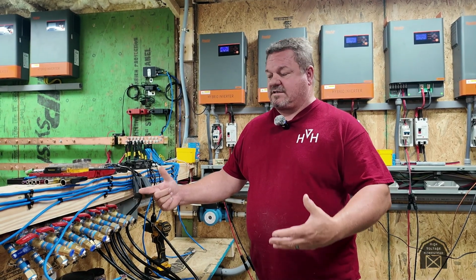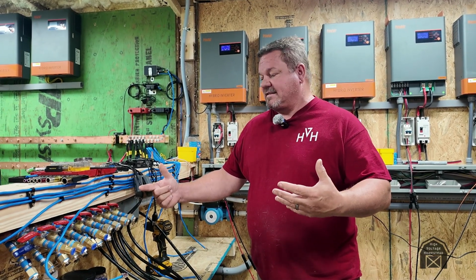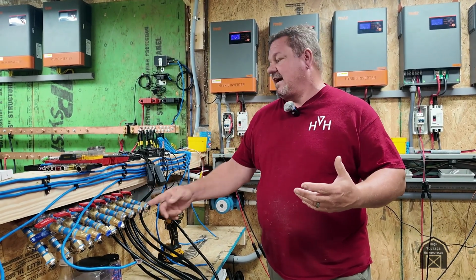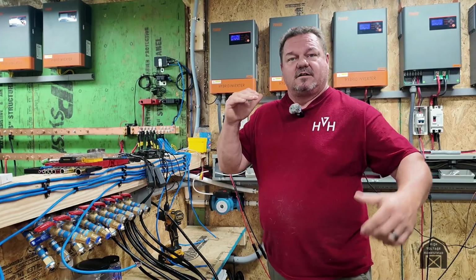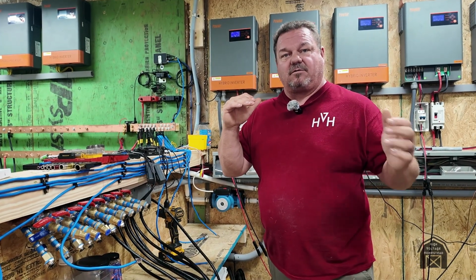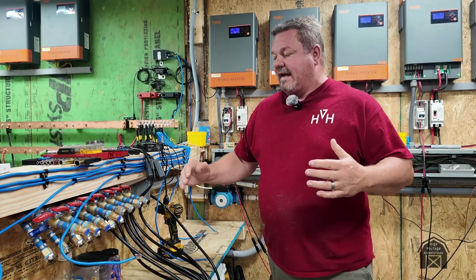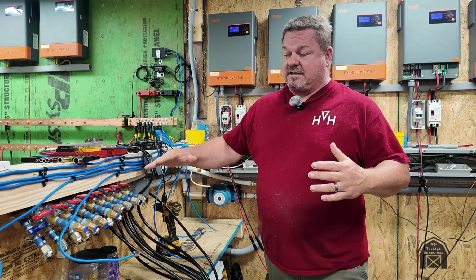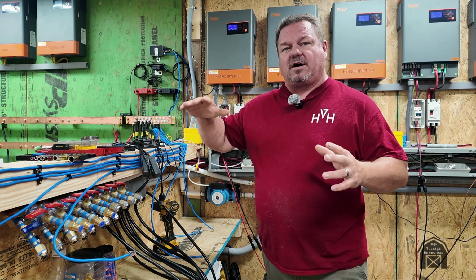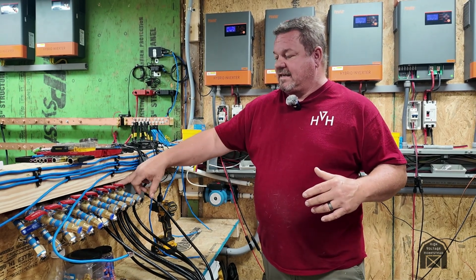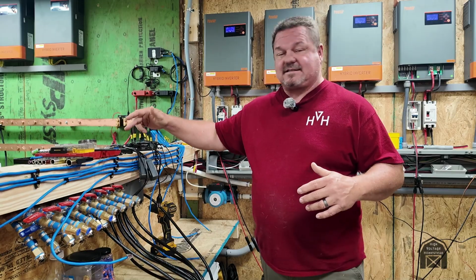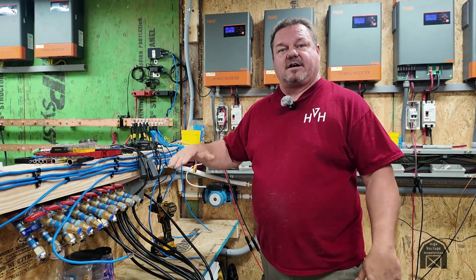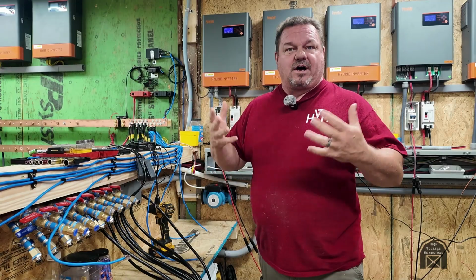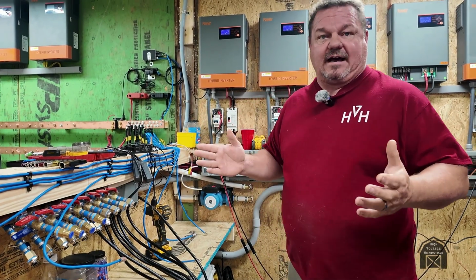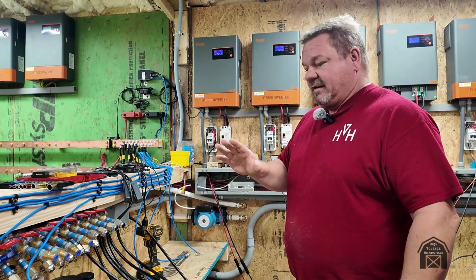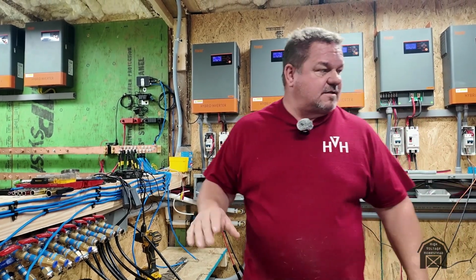Then when it starts up and starts mining and making some heat, the temperature will go up on this line. The first stage will come on, turn on the first smaller pump to just get a little bit of water recirculating through there. I would imagine the temperature will still climb because the one little pump is small. But then once this reaches a preset second temperature, it'll bring on the real pump, because at that point they'll be warmed up enough they should run without any issues. That's the way it's planned to work.